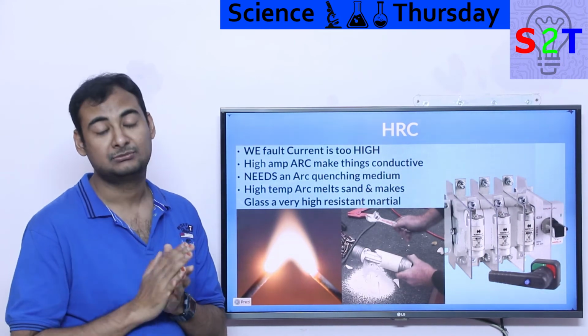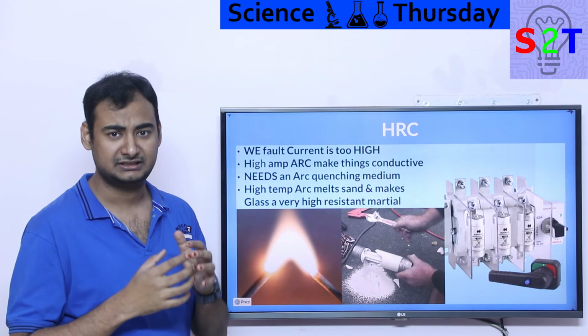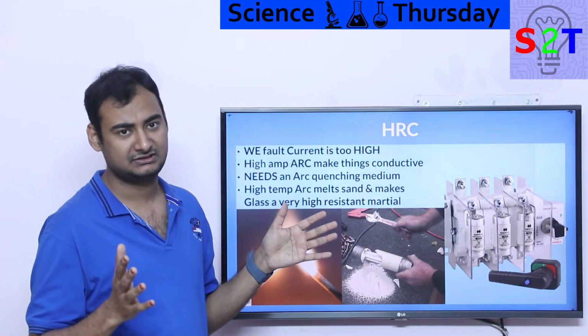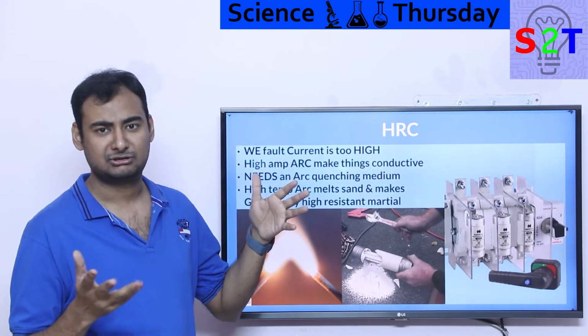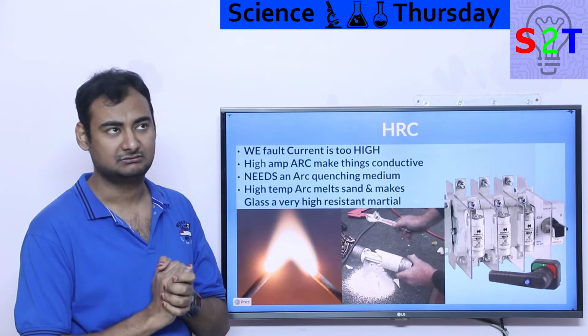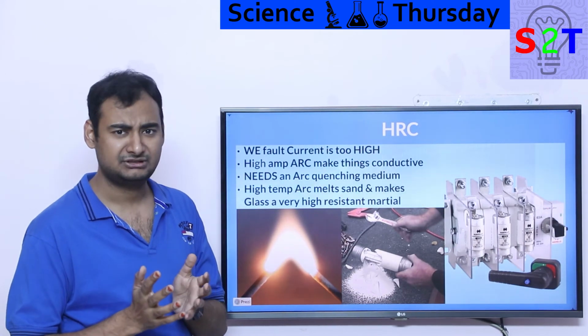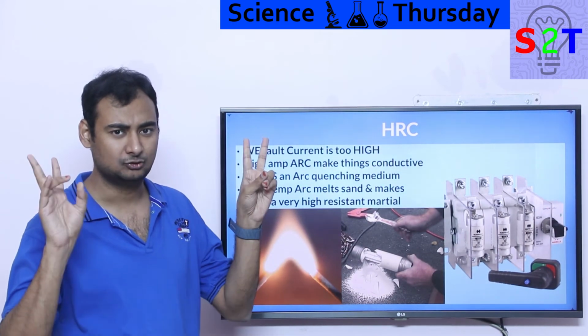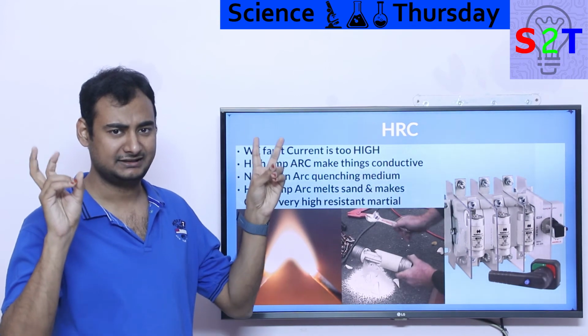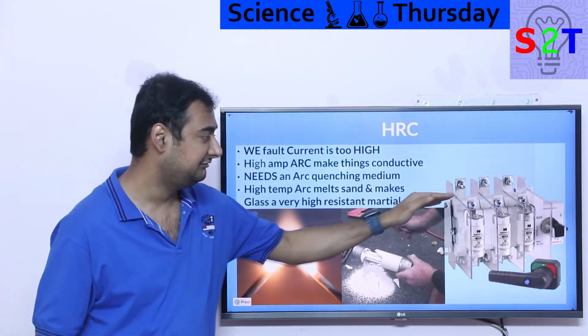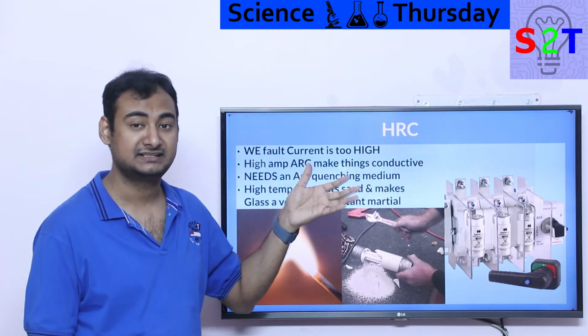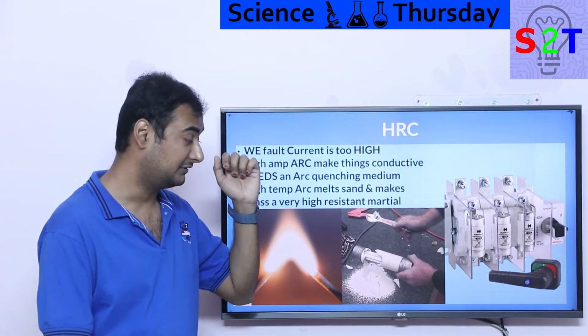And when you are talking about high rupture capacity, especially in substation-size systems or for a big building, you're talking about like 12 kV or even 1000 volt systems, you may find something weird. It's like, dude, why the heck does this fuse have a quote unquote plunger in it? Why is there a plunger? Generally that is done for 3-phase systems. For example, for building elevators, these things are kind of common. I provided a video down below.